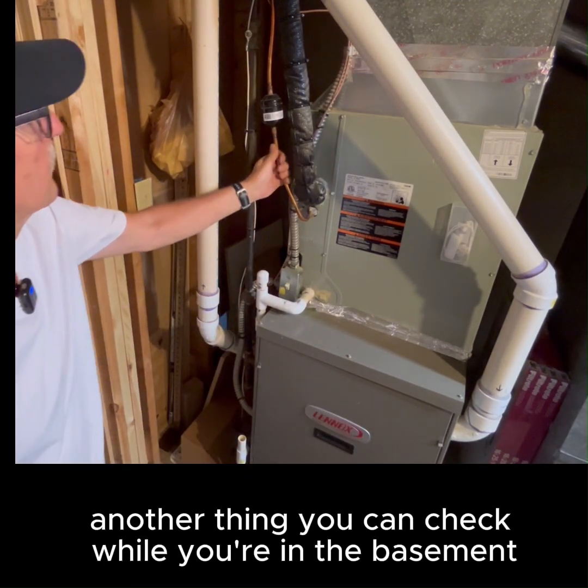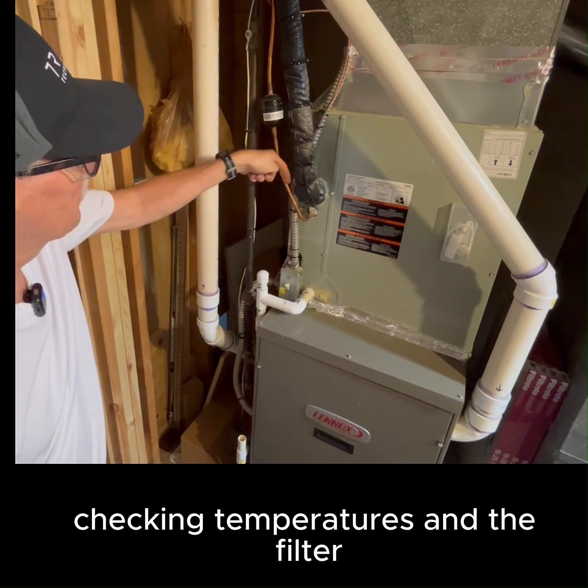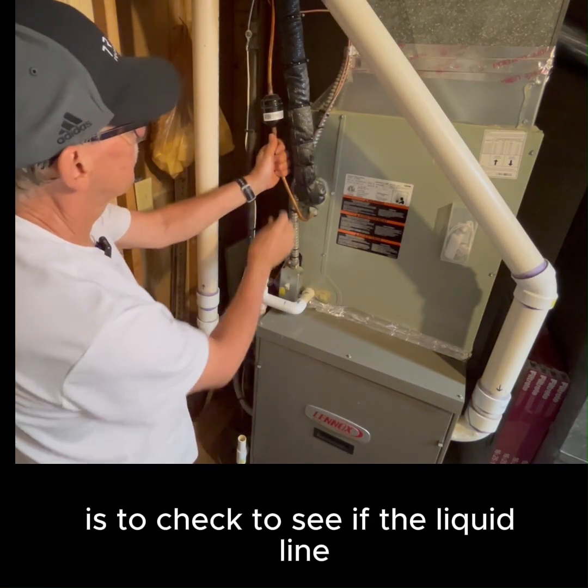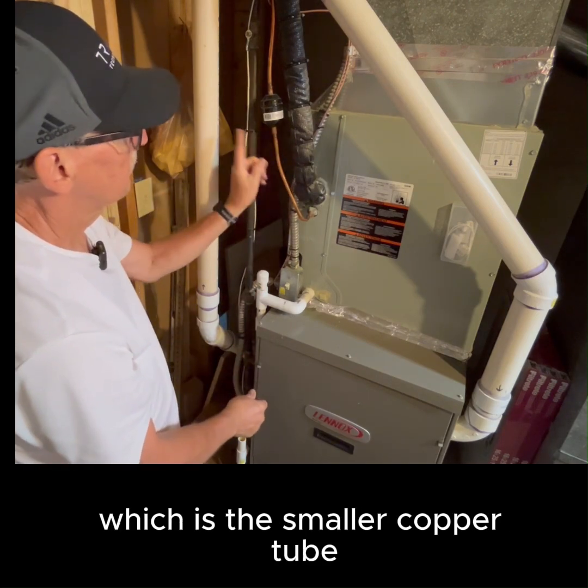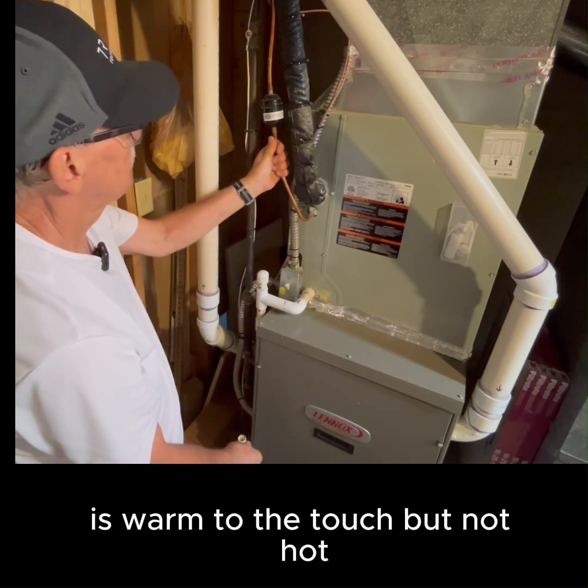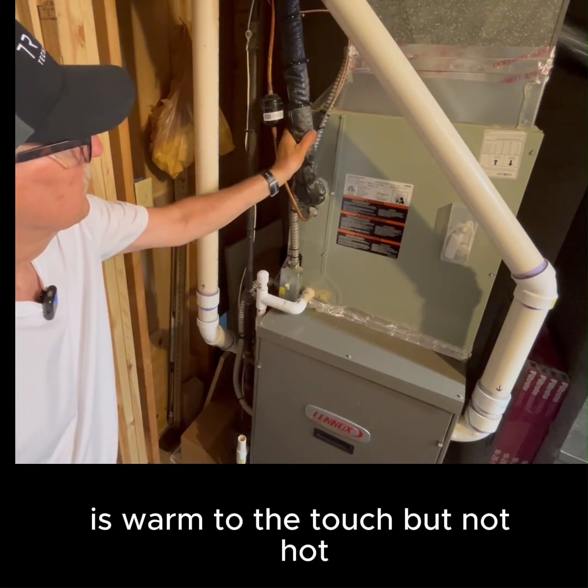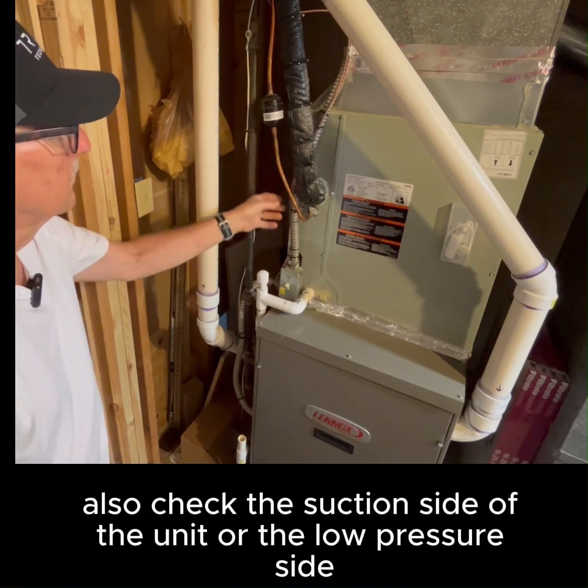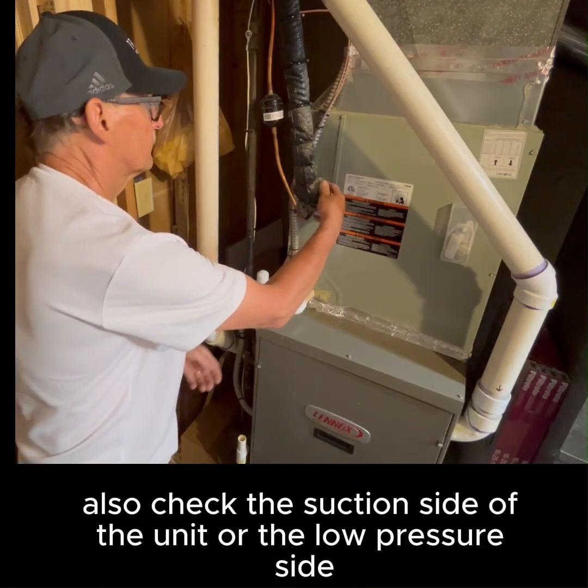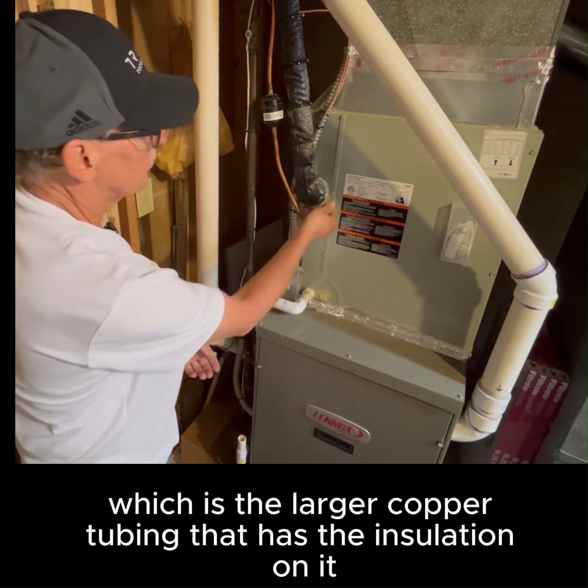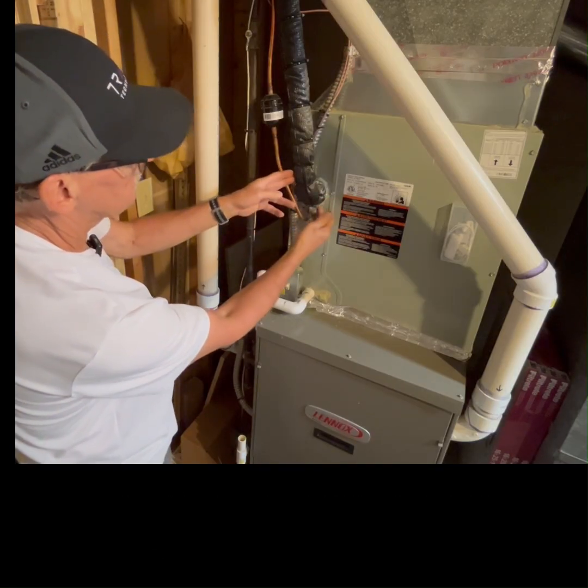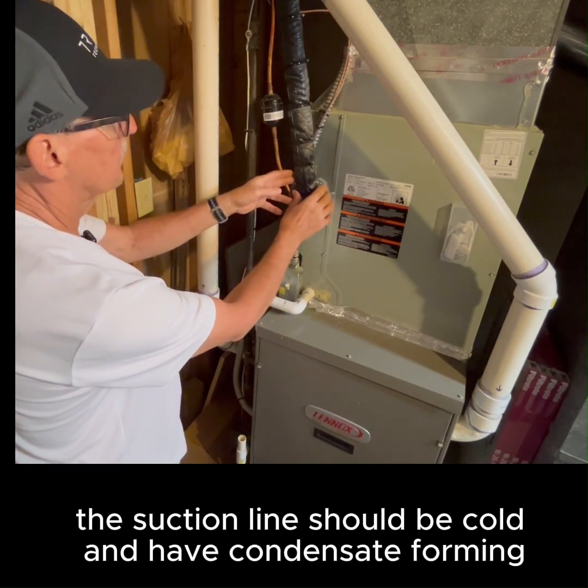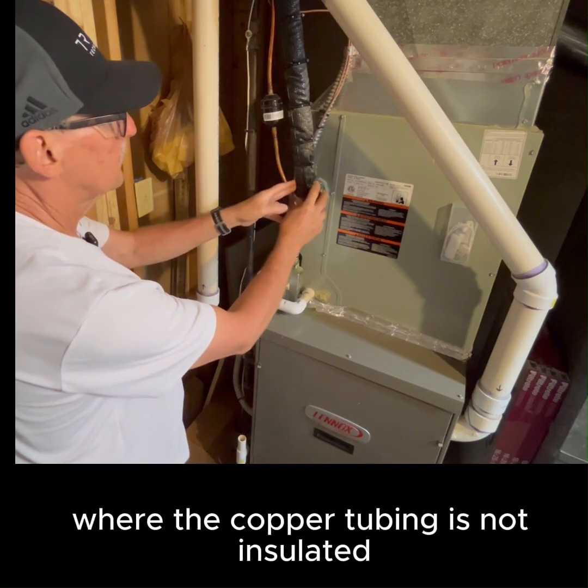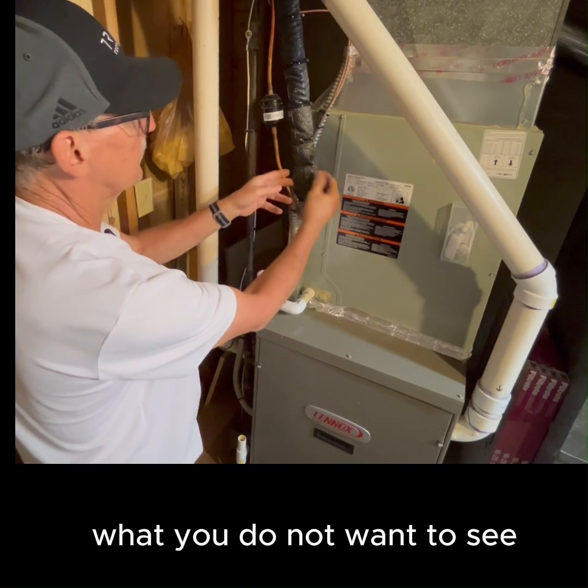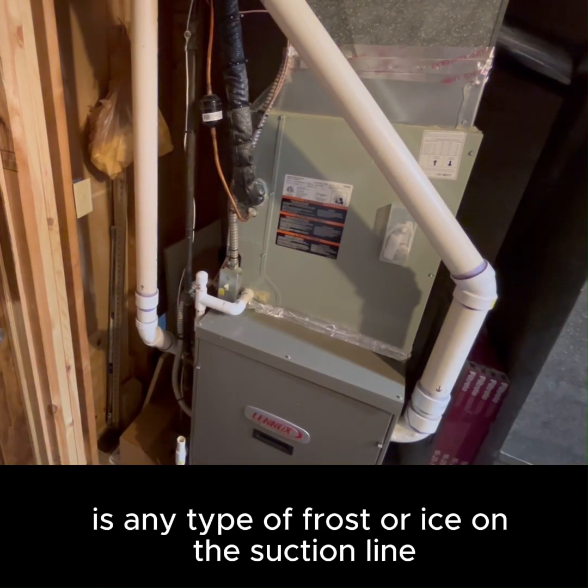Another thing you can check while you're in the basement checking temperatures and the filter is to see if the liquid line, also called the high pressure line, which is the smaller copper tube, is warm to the touch, but not hot. Also, check the suction side of the unit, or the low pressure side, which is the larger copper tubing that has the insulation on it. The suction line should be cold and have condensate forming where the copper tubing is not insulated. What you do not want to see is any type of frost or ice on the suction line.